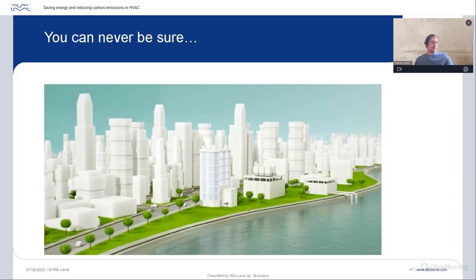Yes. So, okay, now we've talked about market tolerances in sizing and a lot of uncertainty. And that is what we've seen. Actually, it all started to be very clear in the US market in the late 90s or early 2000s. The trend was seen that a lot of these high-end buildings, skyscrapers, couldn't cool enough in the summertime. Every piece of equipment, according to the tech spec, was delivering what was asked for. But still, the temperature was not met. Even if the chillers were operating at full flow rate, they couldn't achieve the 20 to 21 degree set point in the office spaces or in the residential spaces.